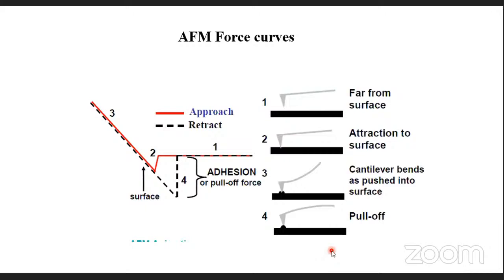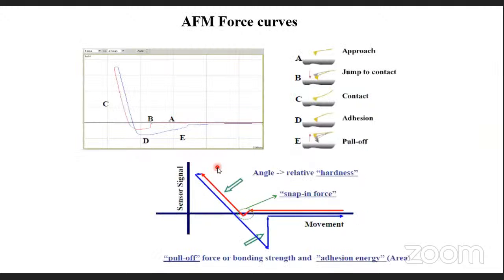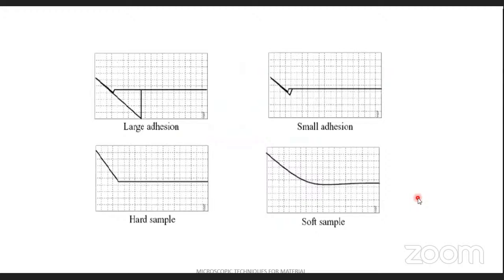The force-distance graph shows far from surface, attraction to surface, contact, pushing inside, and pulling off. You get adhesion force — how much adhesion your sample has — and pull-off force. The graph shape changes depending on the sample: large adhesion gives a deep pull-off curve, small adhesion gives a shallow one. Soft samples show one type of curve while hard samples show another. This is the snapping force and adhesion energy information from your sample.